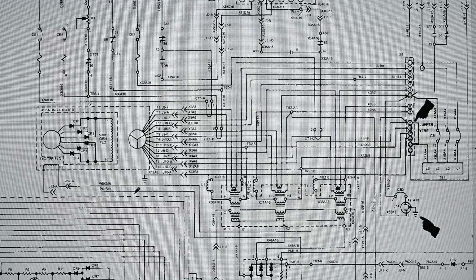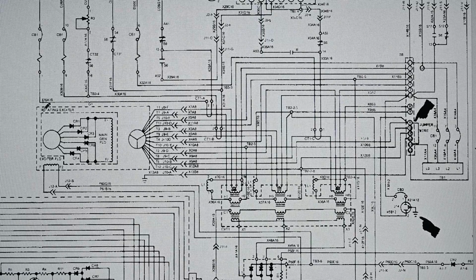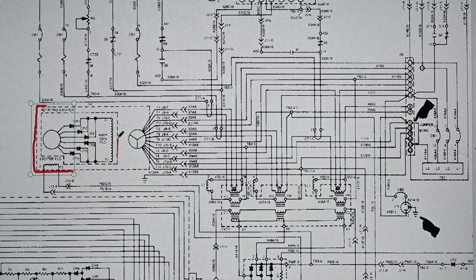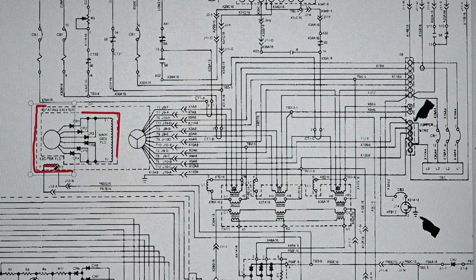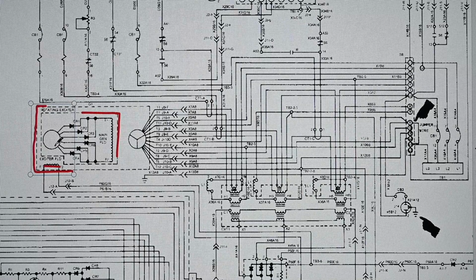So before I look at the voltage regulator circuitry, just a quick look at the main brushless alternator. So you can see the entire generator or alternator assembly is represented inside this dashed line. And this dashed line right here represents the rotating exciter. So everything inside this dashed line is rotating inside the generator. So this is the main field winding right here. So you have the DC voltage that's applied to this field from the regulator circuitry that we'll look at in a moment. And that causes a voltage to be created on this 3-phase rotating exciter right here.